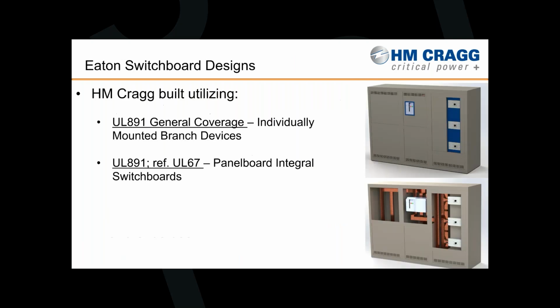Under the switchboard category, this means the ability to utilize our UL 891 general coverage, which covers switchboards with individually mounted devices—defined by main breaker and branch breakers all being in their own isolated compartments or buckets—or to utilize UL 891 referencing UL 67, meaning group-mounted distribution with more density, giving us both a UL 891 general coverage section and a group-mounted distribution section referencing UL 67.